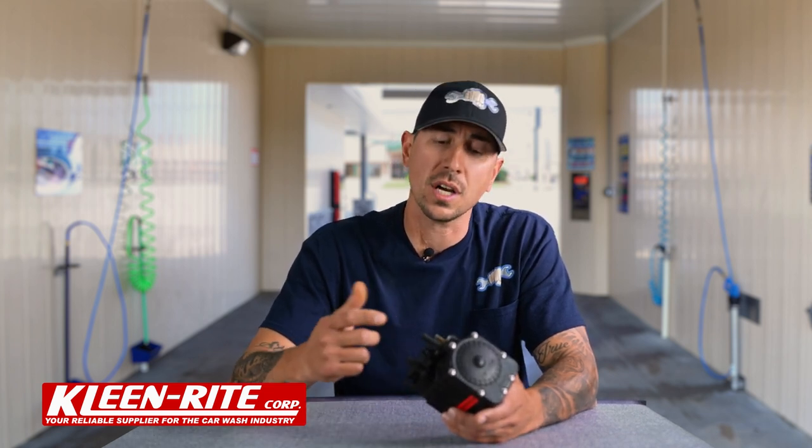My favorite part — troubleshooting. When it comes to a Flojet there are really only three things to consider: air supply, suction, and discharge. On the airline, we're looking for a minimum 20 PSI supply of clean, dry air — as long as we're supplying those two things the air side should be good. On the suction side, the biggest thing people run into is dirty or bad foot valves. As long as that foot valve is clean and working properly, this pump will easily draw fluid up into it.